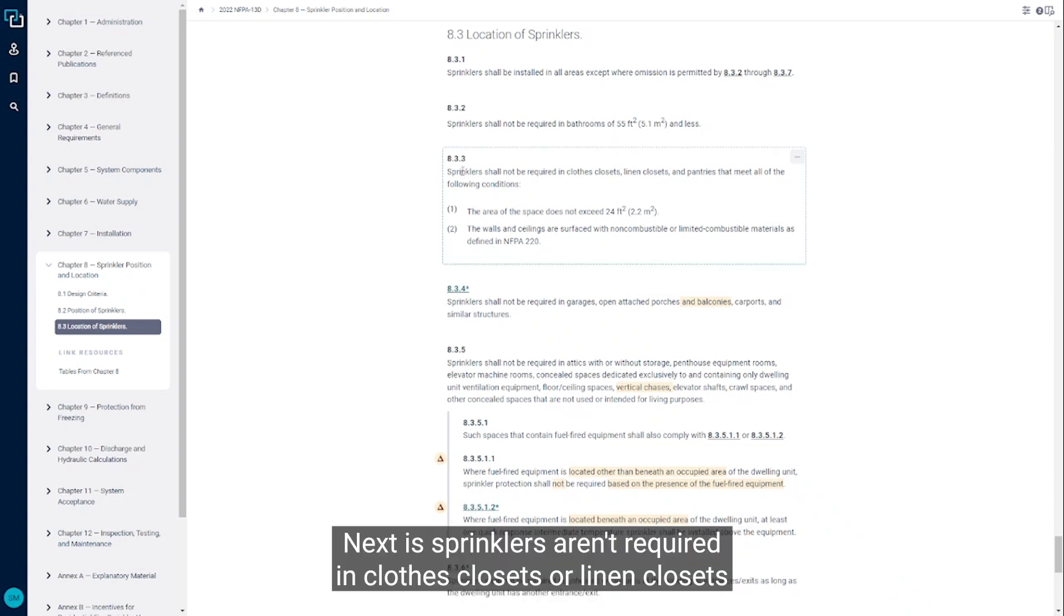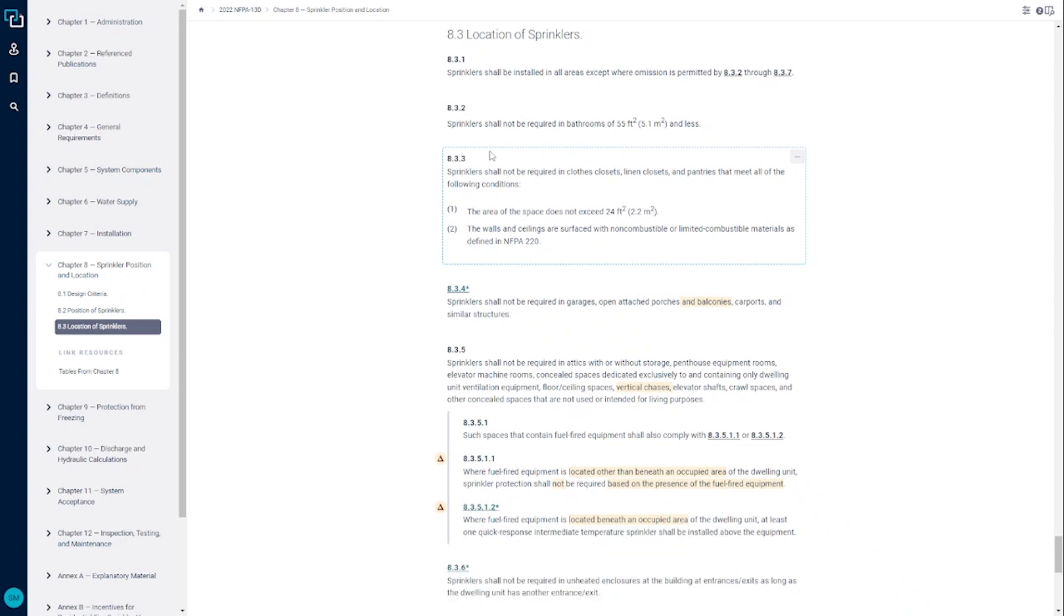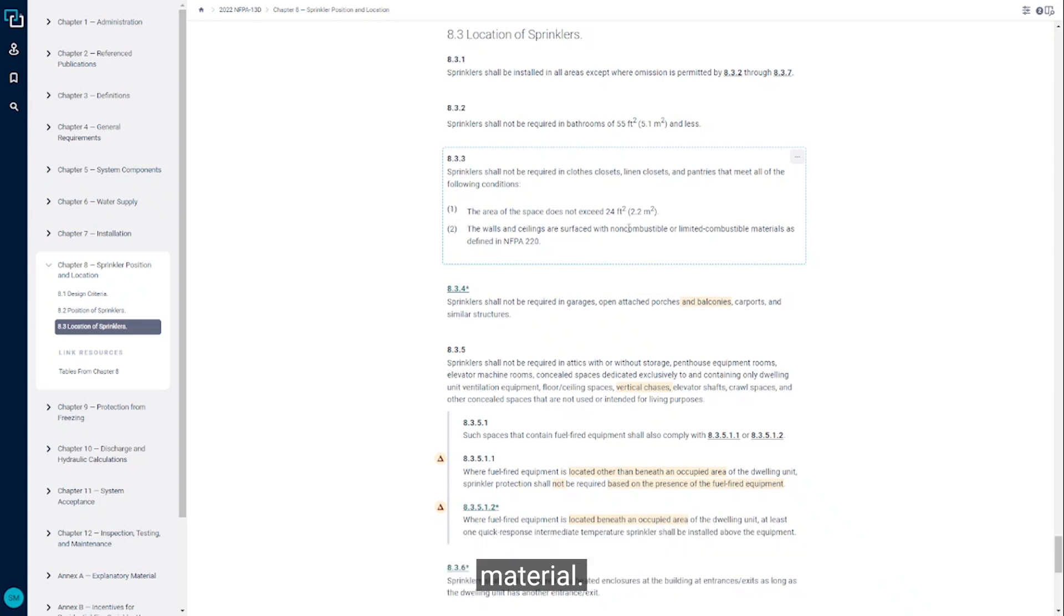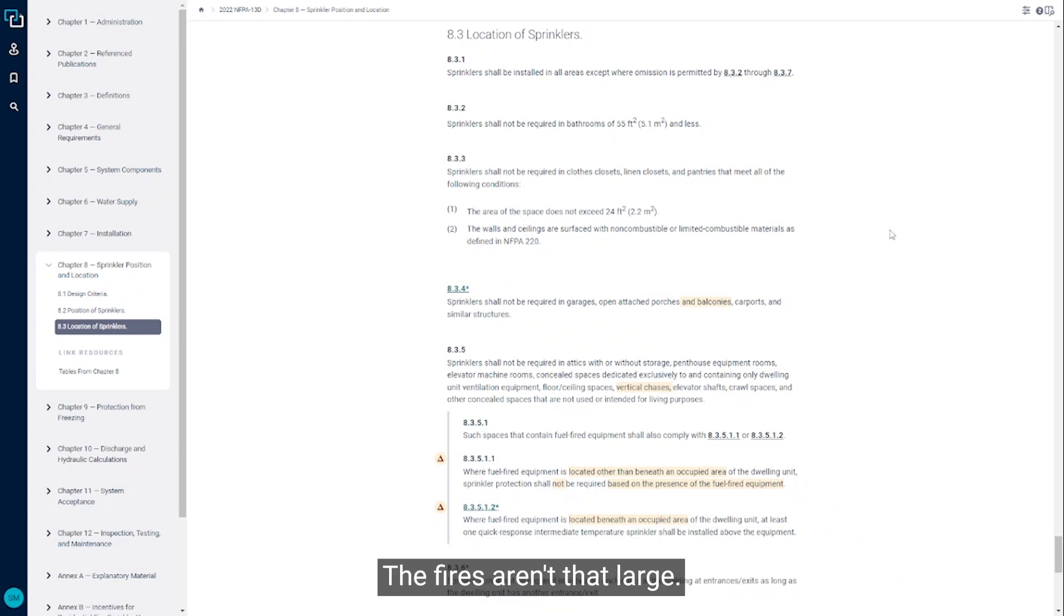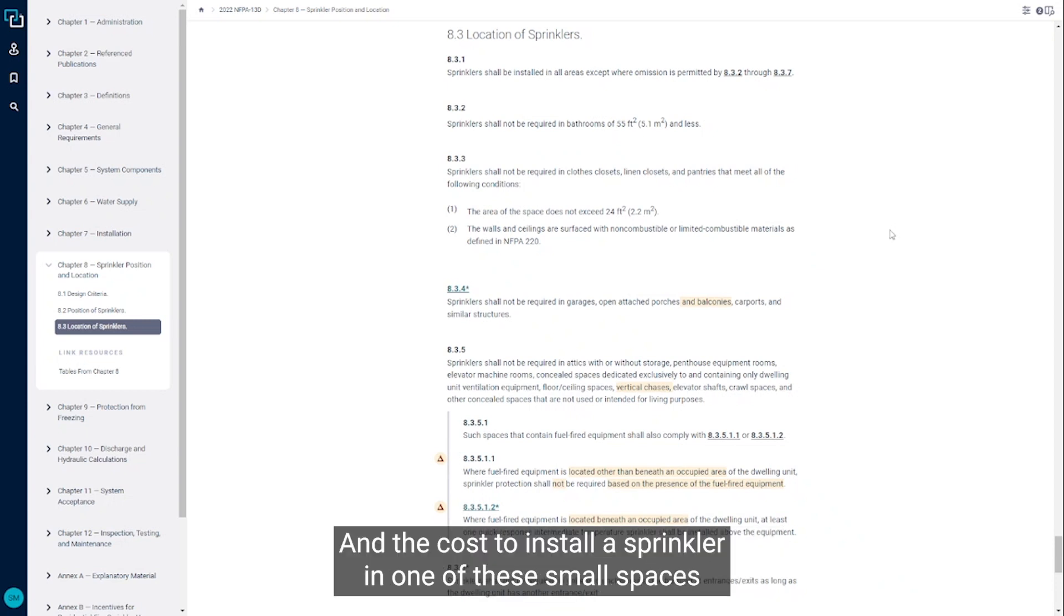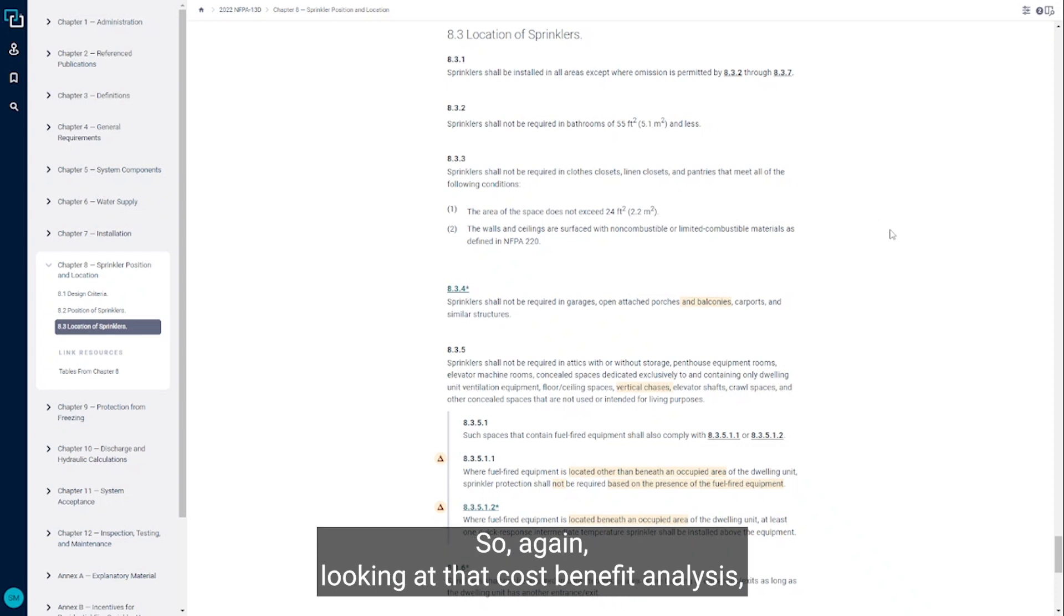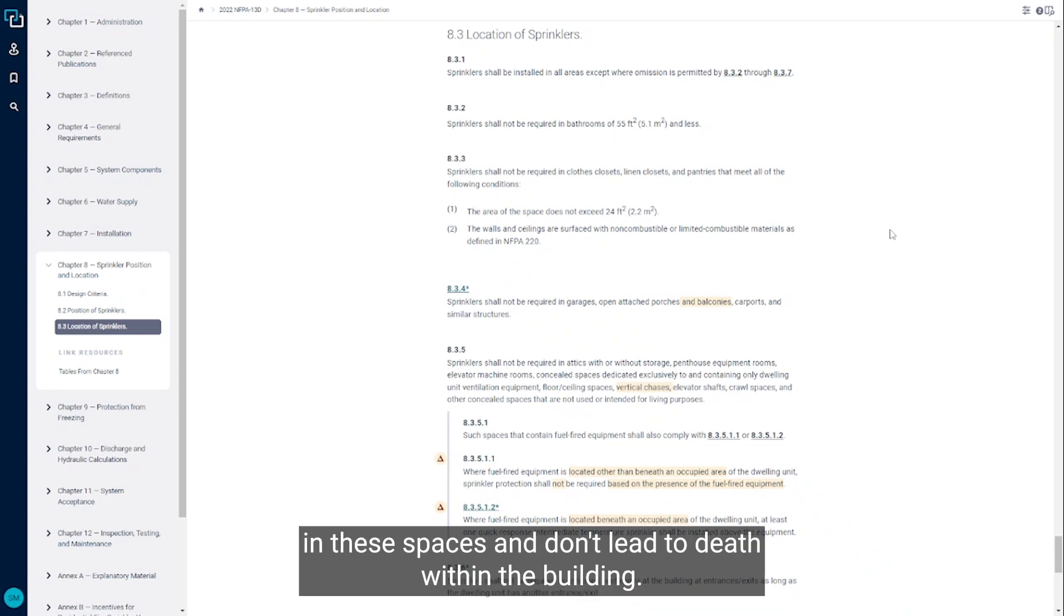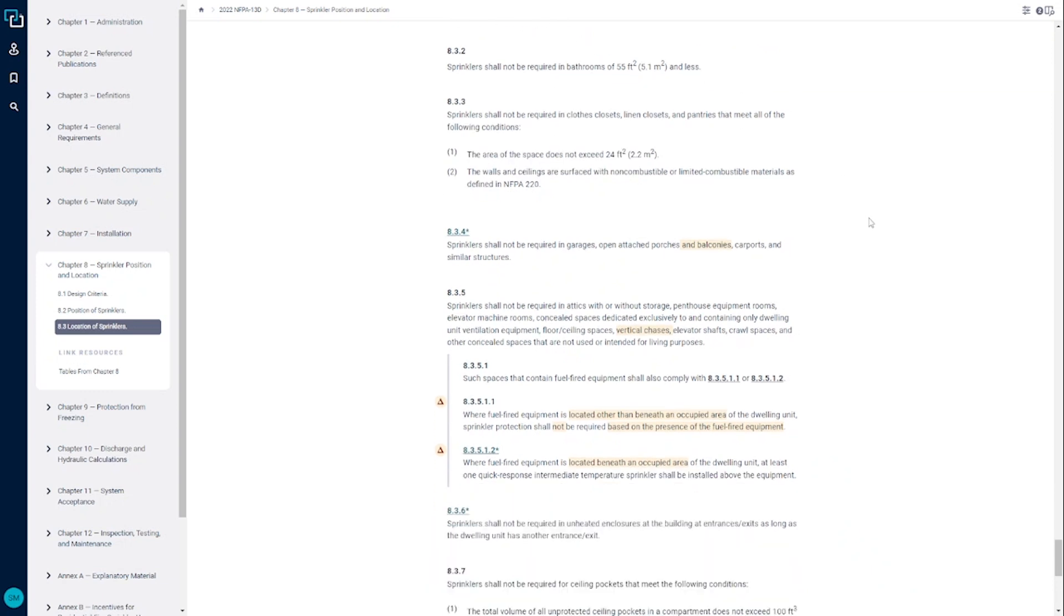Next, sprinklers aren't required in clothes closets or linen closets, as long as they're less than 24 square feet or 2.2 square meters, and they're surfaced with a non-combustible or limited combustible material. This is being provided because these are relatively small spaces, the fires aren't that large, and the cost to install a sprinkler in one of these small spaces is actually relatively high because they're so small and there's typically a lot of them in a building. The statistics don't show that fires are that common in these spaces or lead to death within the building, so we are allowed to omit them from those spaces.